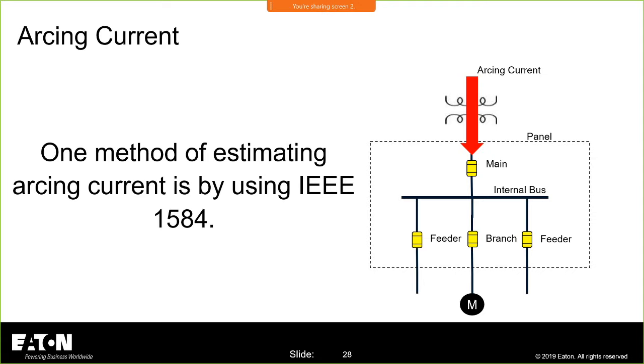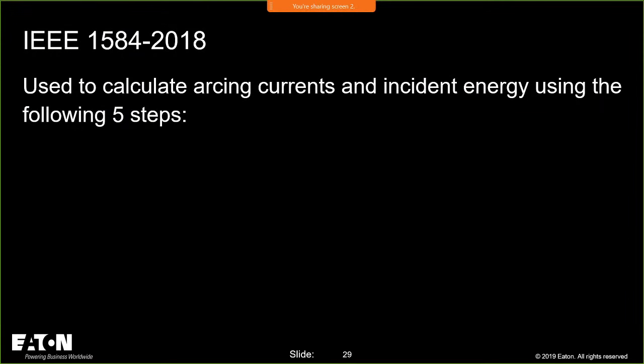Now, 1584 gives us the equations to calculate both of those values of arcing current, but it's important to understand the current flow, and we're going to talk a little bit about current flow of the arcing currents and the clearing times. But 1584 2018 is that which we use to calculate incident energy, and they do it in 5 steps. There's 5 basic steps that we follow when we're doing our 1584 calculations. So just to give you a for instance, let me just get my computer working here. Okay, all right, it's working again.